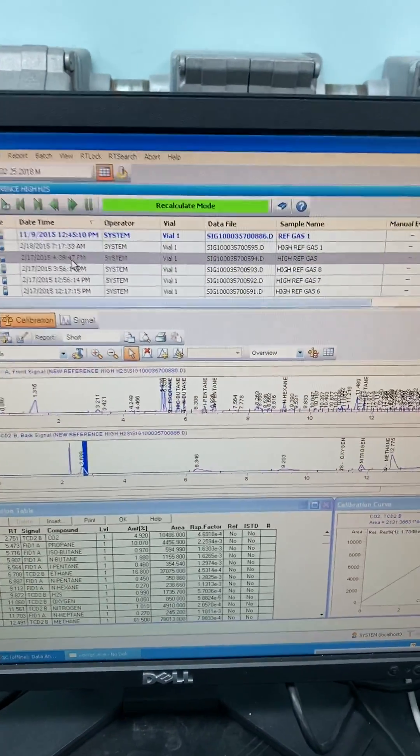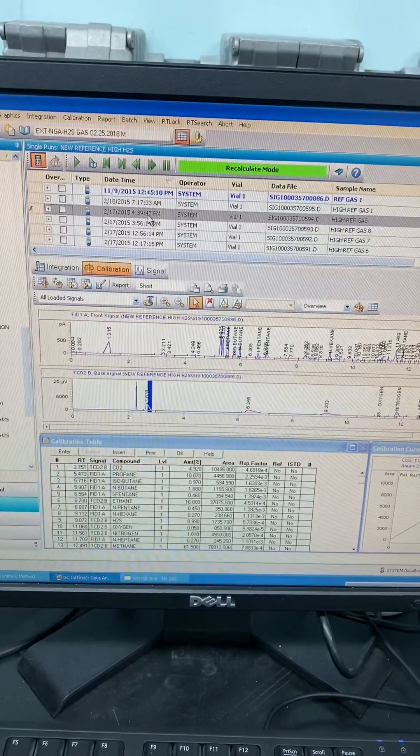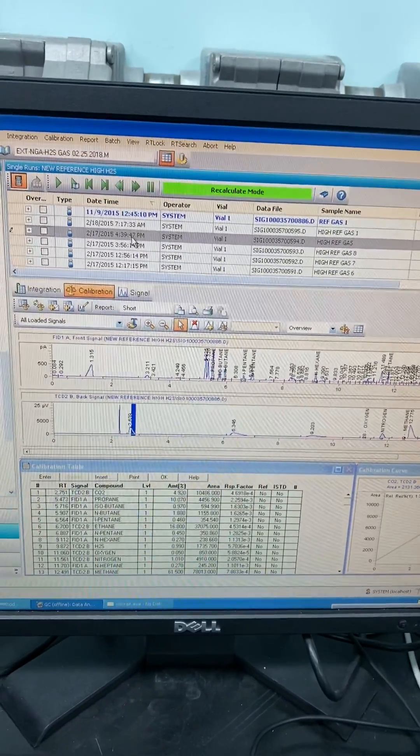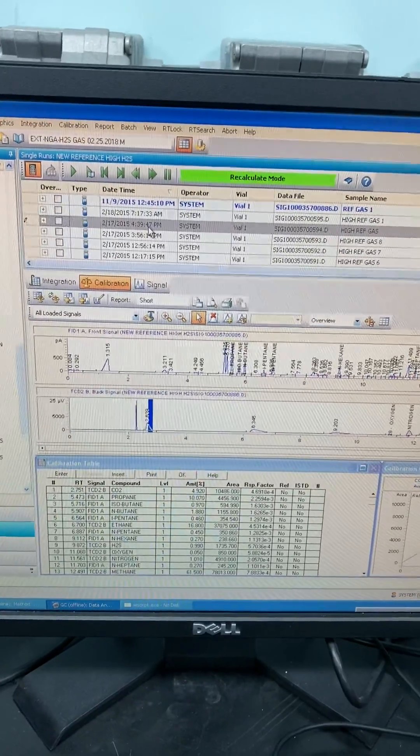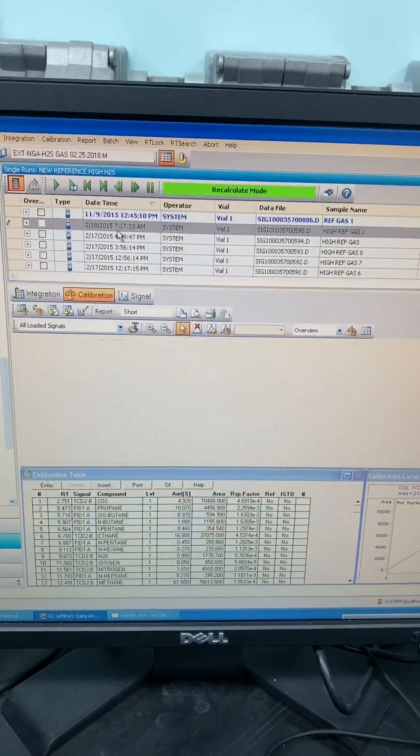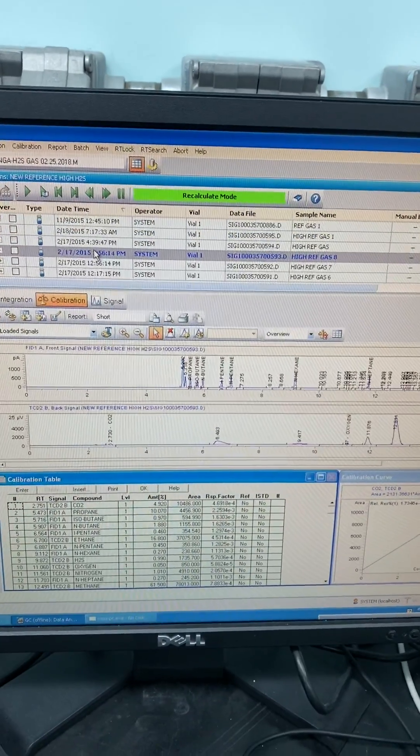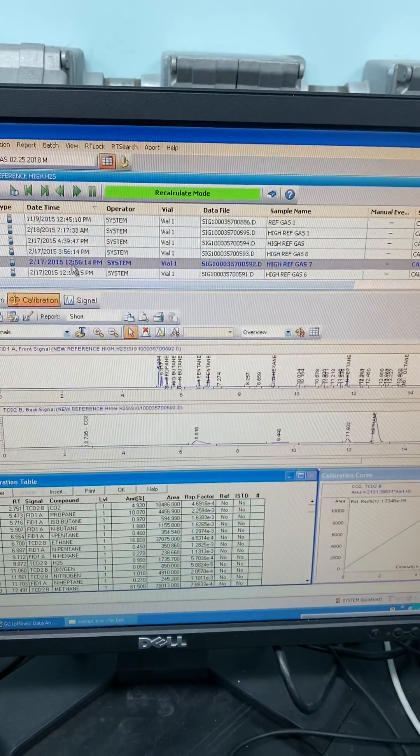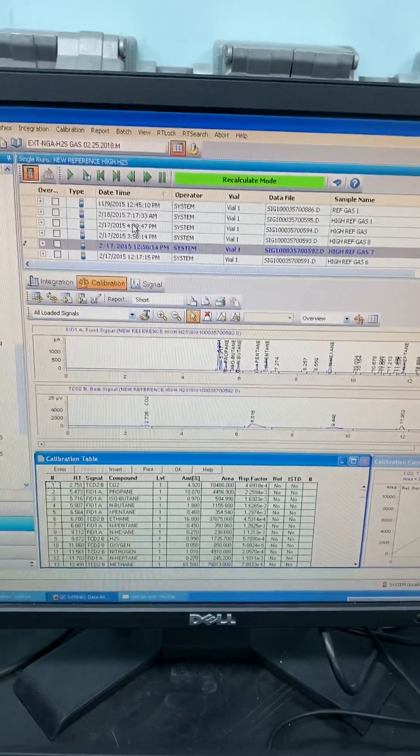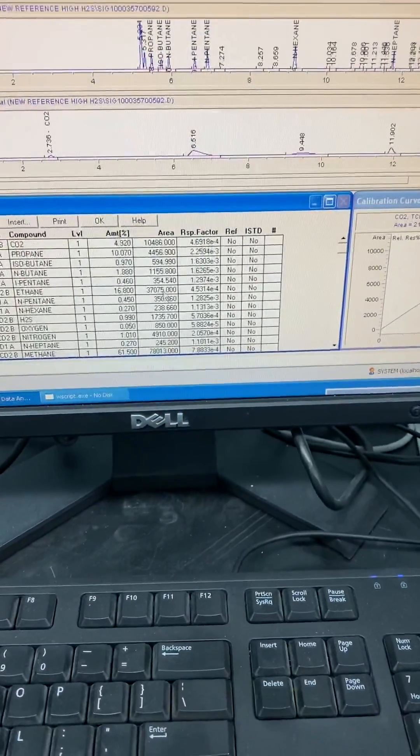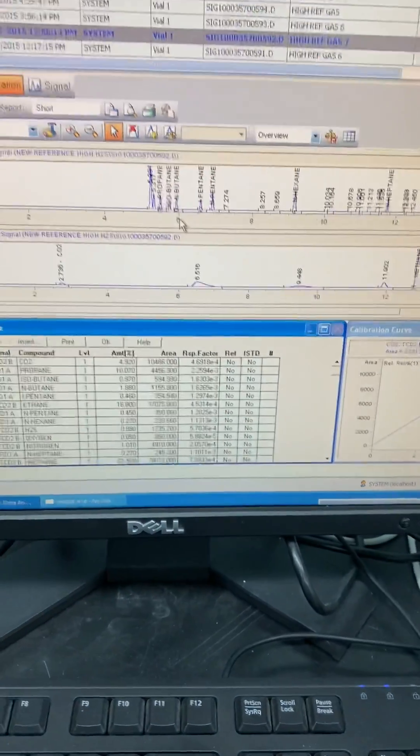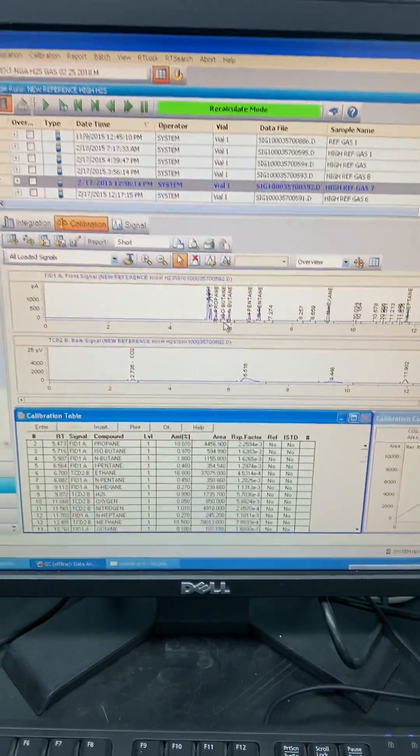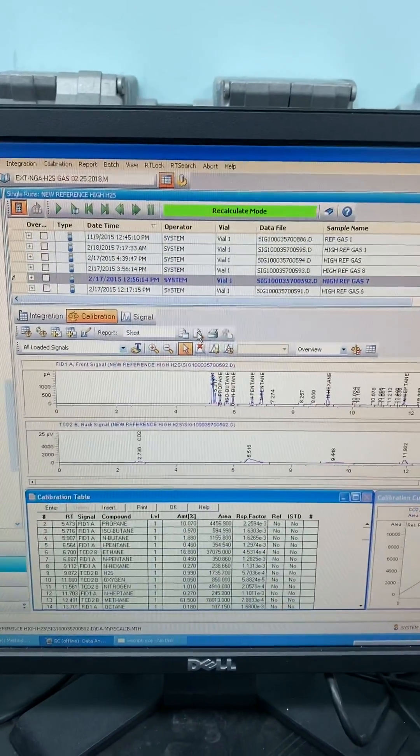How to select the best reference run? You have to inject certified reference material to your gas chromatography several times until you have two or three good repeatable runs. How to know the good repeatable runs? Like I can compare the two runs for the peak areas, the area of each one that we have, and the concentration.